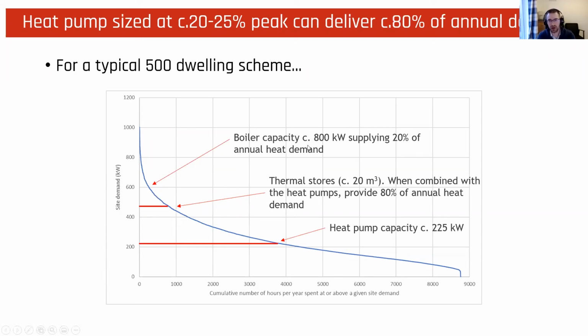This becomes quite powerful when you compare this against trying to do peak demand solely through heat pumps: 1200 kilowatts of heat pump. One, that needs a lot of space, and two, it's extremely expensive. So these are the kind of considerations, and using thermal store to play around with the difference between peak demand that's coming from the site and when the heat pump can operate, to really reduce that total heat pump capacity while still meeting the end user demands.